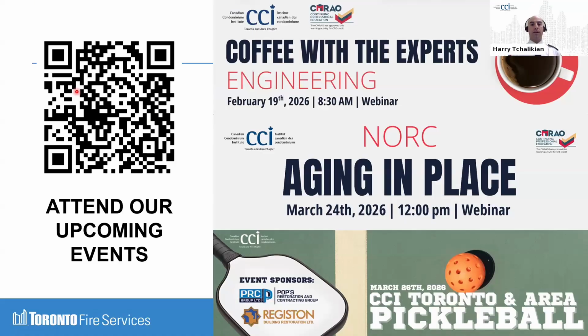Yeah. So if there's makeup air for the corridor only, but the suites are on a radiator, then you do not need carbon monoxide alarms in the suites, unless they fall under the original requirement of sharing a wall, floor, or ceiling with the service room. Weather stripping, though, is heavily regulated because of smoke travel issues. So under the NFPA 80 standard for doors, you're not allowed more than a 3 millimeter gap on the sides and a 6 millimeter gap on the bottom. That is the maximum size of gap you are allowed on your suite doors between the suite and the public corridor. So if your corridor is served by makeup air and that weather stripping is in place, it shouldn't be an issue. But please make sure that you always maintain your weather stripping to those standards.